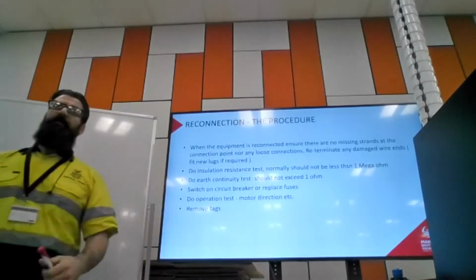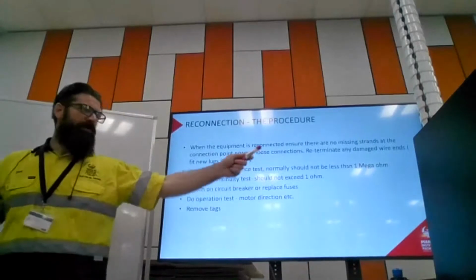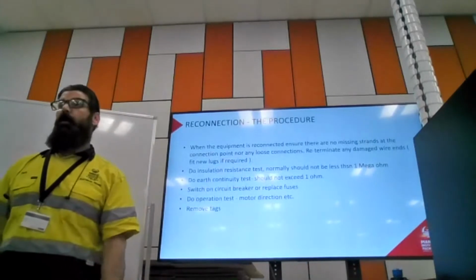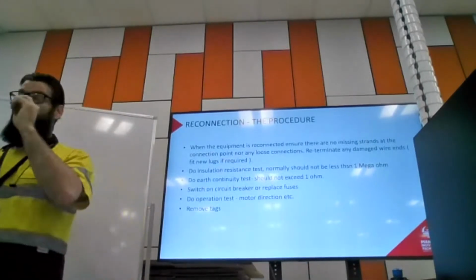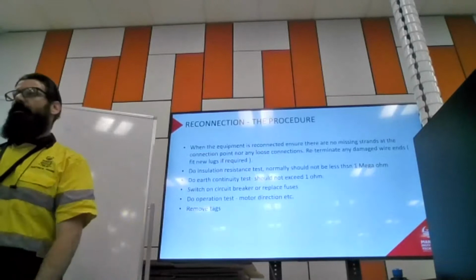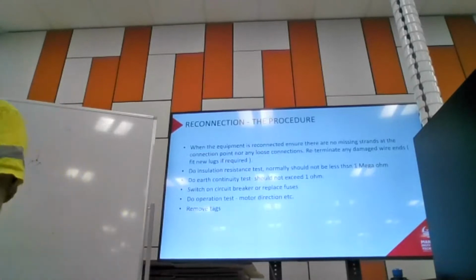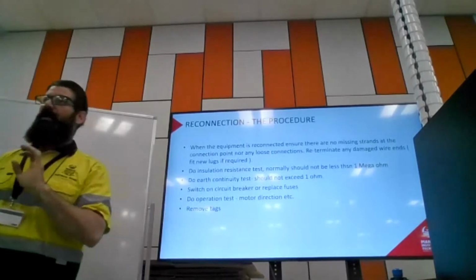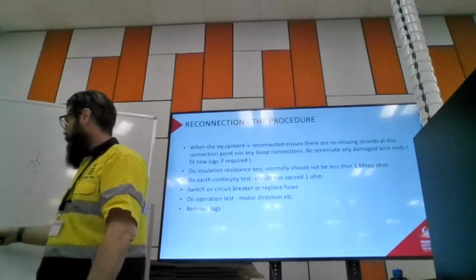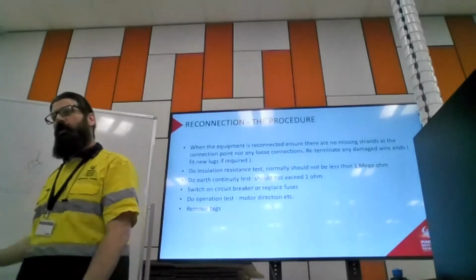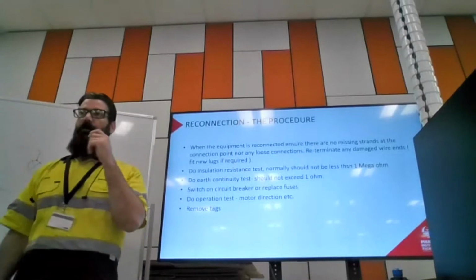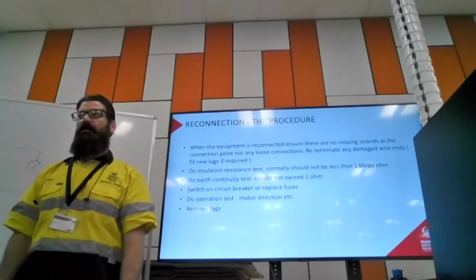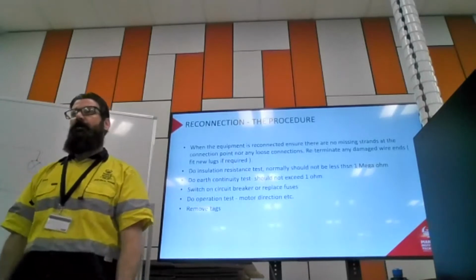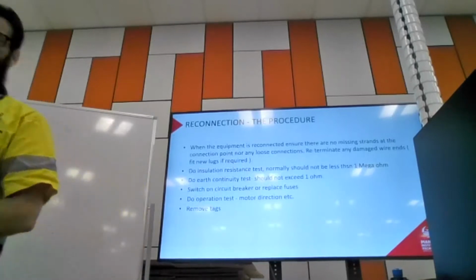Now, in most cases, you'll find that even a water heating element will still be more than 1 megohm, but sometimes it won't, particularly in an older one. Even a little bit of moisture in there can drop that insulation resistance, but it's not necessarily super dangerous. So only for water heating elements, we give a little bit of allowance that, okay, it's probably going to get some moisture in there at some point. And so we can allow an insulation resistance of as low as 10,000 ohms. As long as it's more than 10,000 ohms, it's okay.